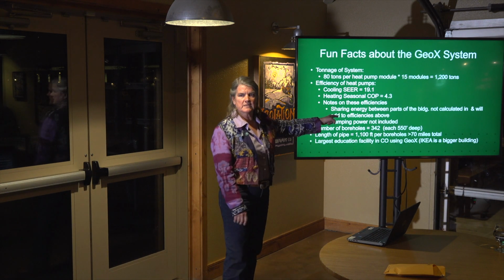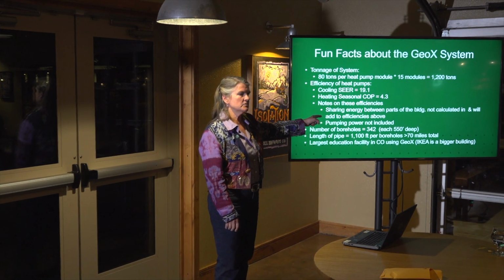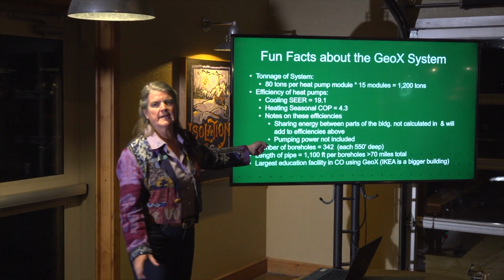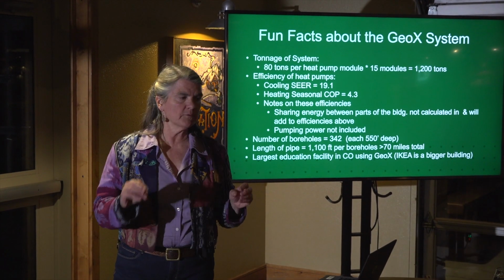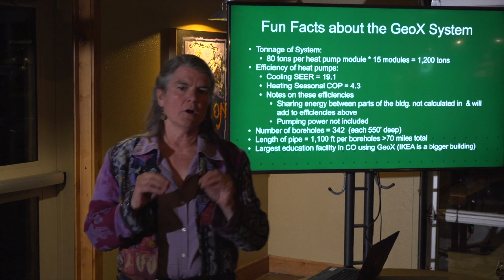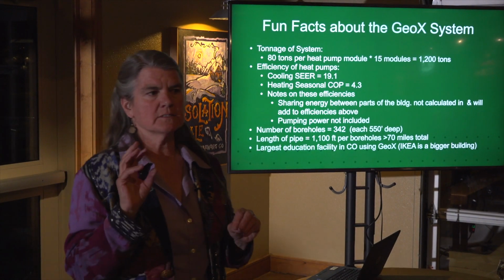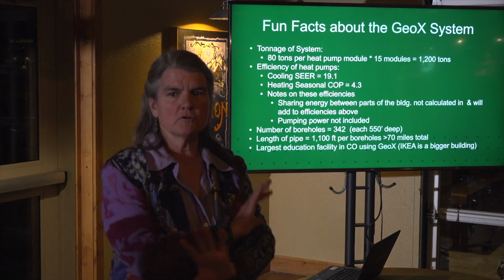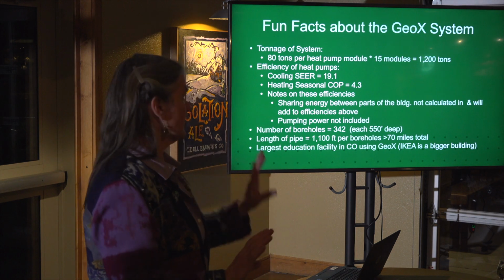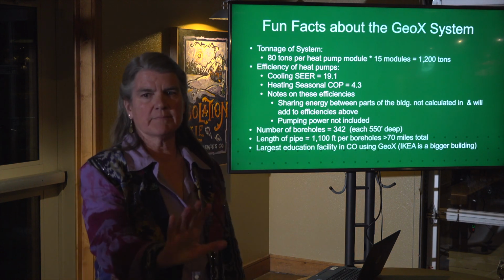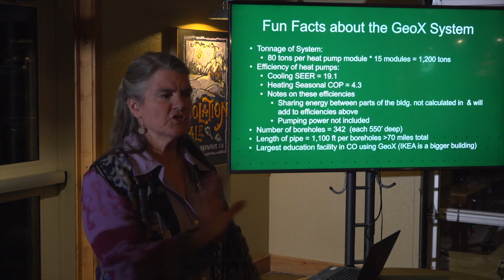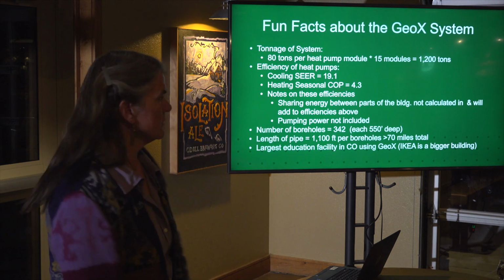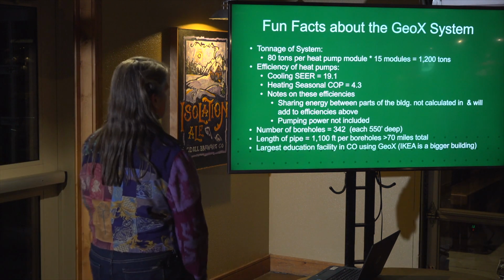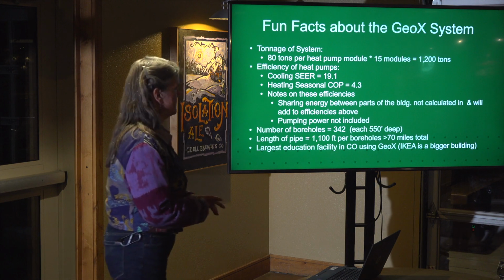Here's an interesting thing: the tools people typically use to estimate building loads, like Trane Trace, aren't well suited to modeling moving loads in a building. They can model it, but they say that's the worst-case estimate, since any sharing of loads within the building isn't accounted for. And these efficiency numbers also don't include pumping power.